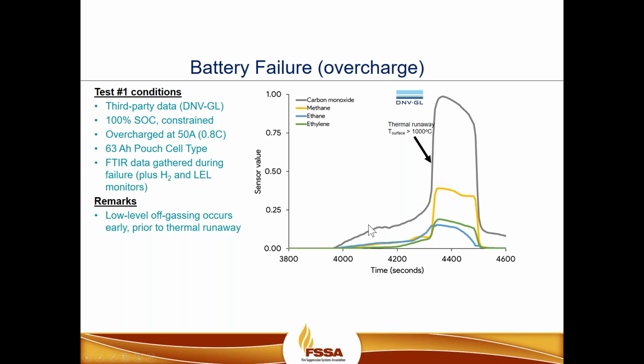So when using, say, LEL detectors, there's no way that we would have been able to have any type of early warning. Of course, at the upper levels, after thermal runaway had already been achieved, an LEL detector would have possibly detected the event.